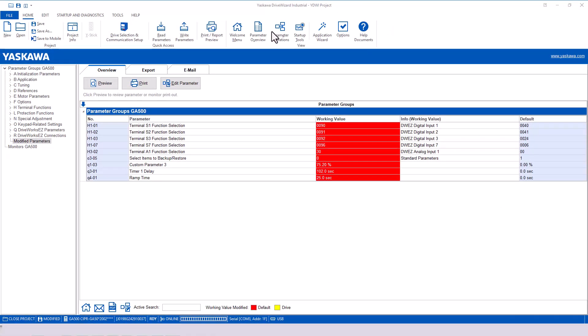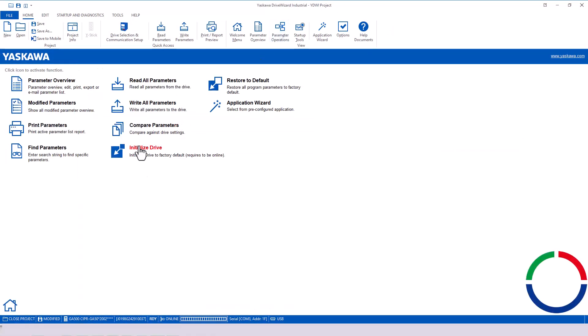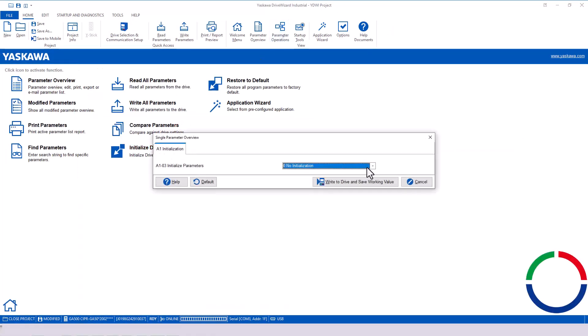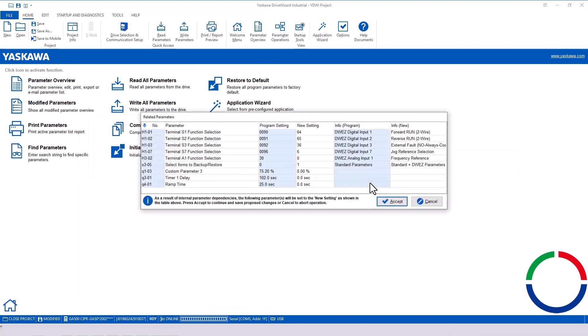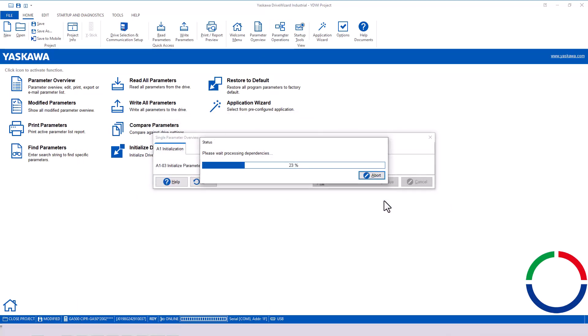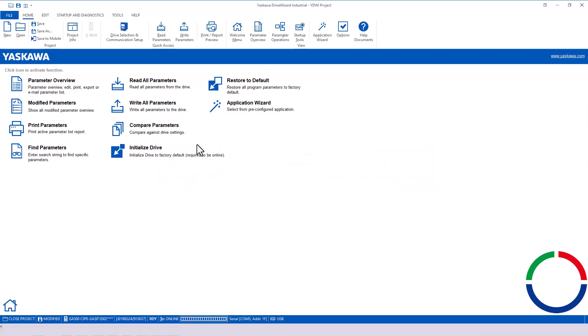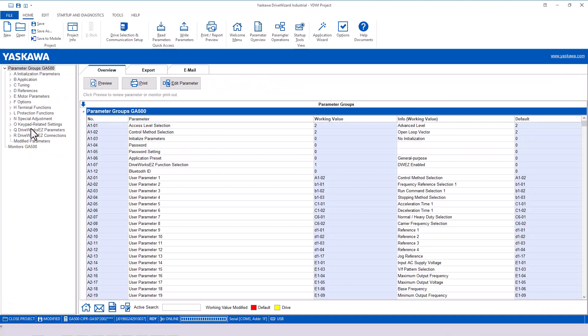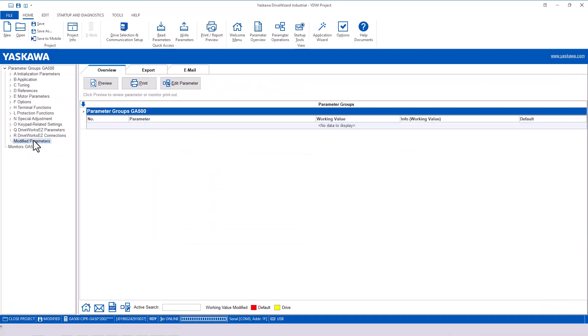A standard two-wire or three-wire initialization will clear out your Q parameters, so be careful before re-initializing the drive, as it will most likely result in an improper DriveWorks EZ program operation.